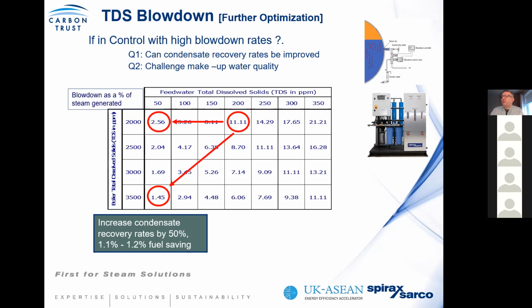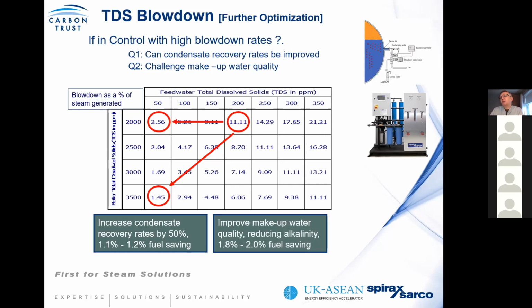So in other words, the feed quality of your boiler water is very important. Depending on the quality of your water, in consultation with your water chemist, you should look to see what the best grade of water is for your application. If you have a high makeup water demand, so in other words, your process consumes a lot of steam, then you should look at the potential for changing the grade of your water. Okay, so again, improving water quality and reducing alkalinity through reverse osmosis water, you can get up to about a 2% fuel saving.